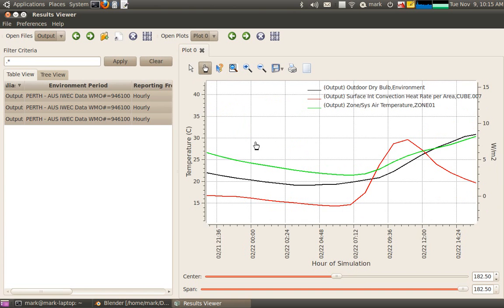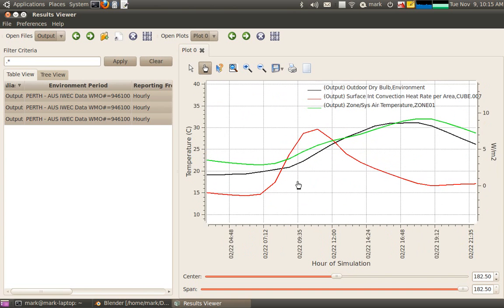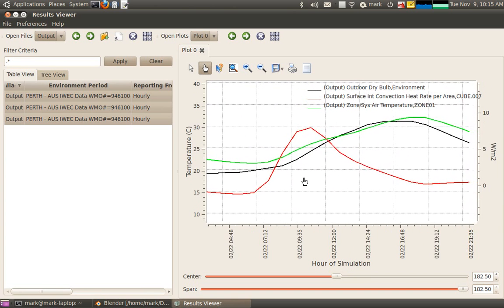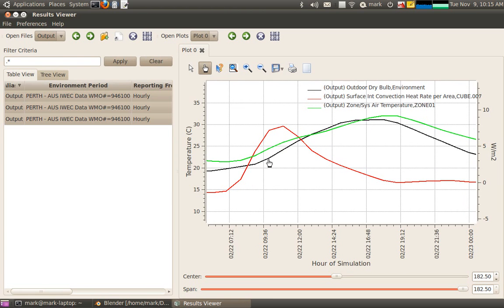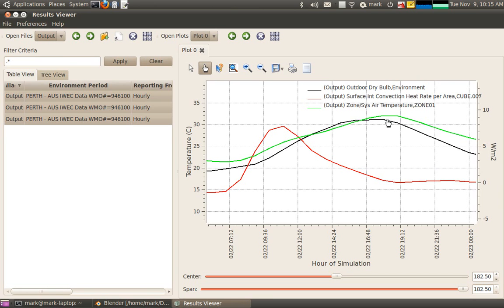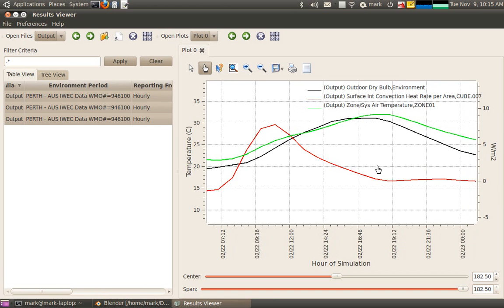Same sort of thing happening as what happened before. We've got that eastern wall. Heat's coming through it in the morning, obviously, when the sun's shining on it. Because of the thermal mass of the 100mm concrete, we've got a bit of a delay between the peak outdoor drybulb temperature and the internal peak temperature.